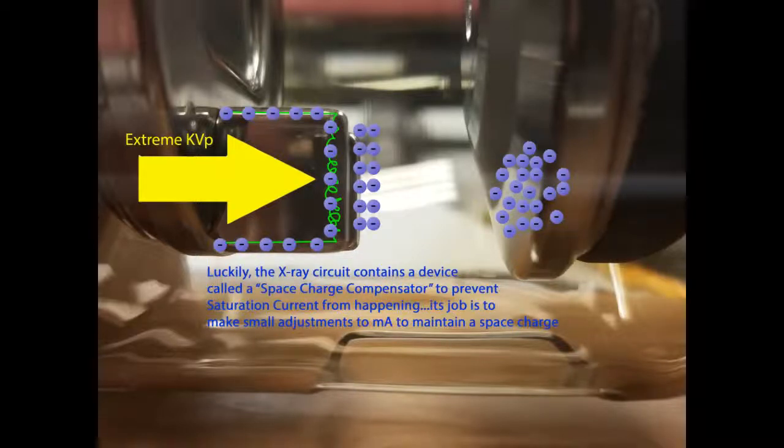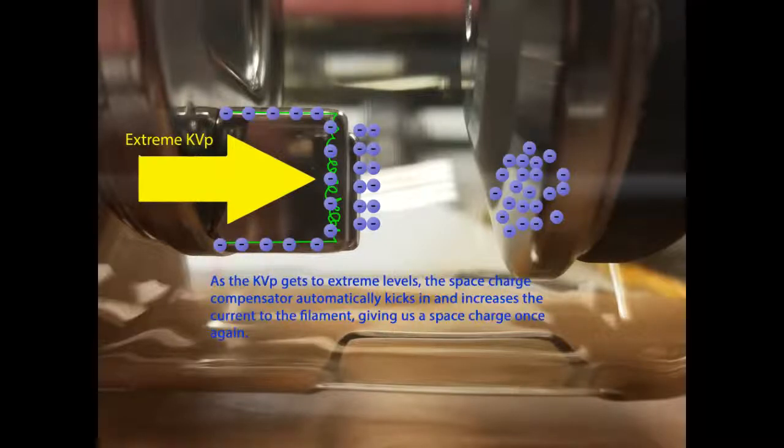Luckily, the x-ray circuit contains a device called a space charge compensator to prevent saturation current from happening. Its job is to make small adjustments to mA to maintain a space charge. As the KVP gets to extreme levels, the space charge compensator automatically kicks in and increases the current to the filament, giving us a space charge once again.